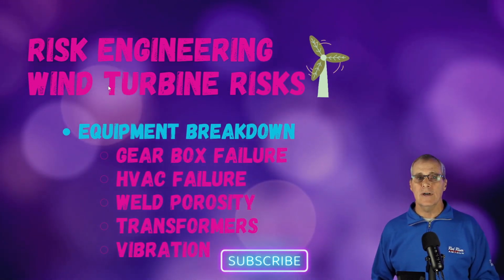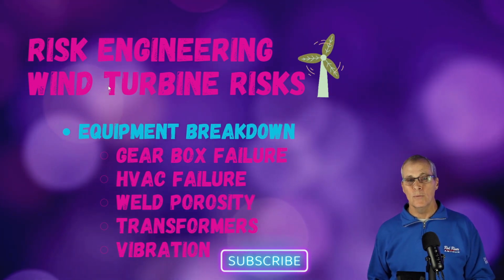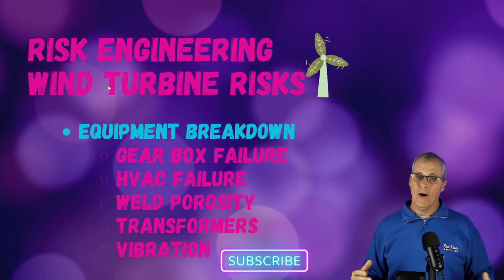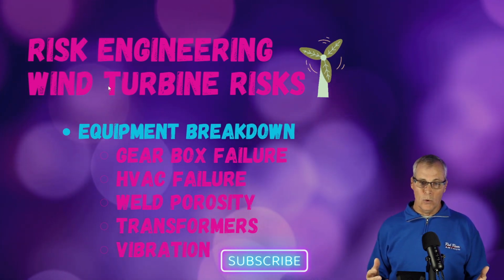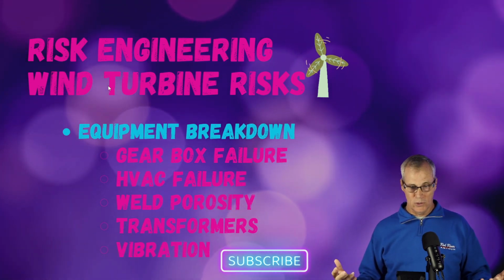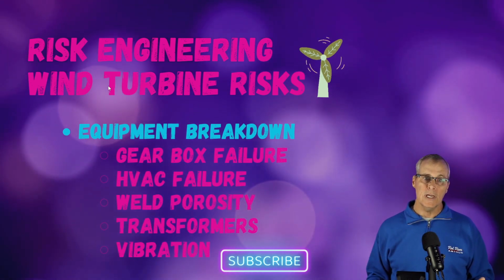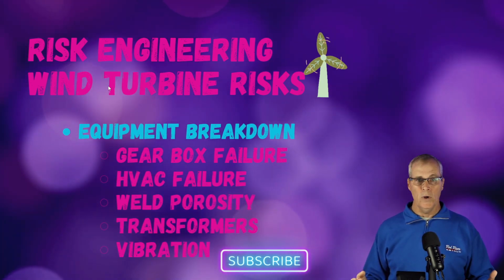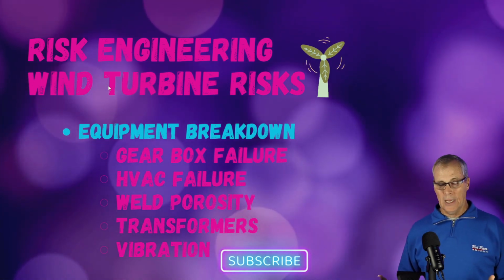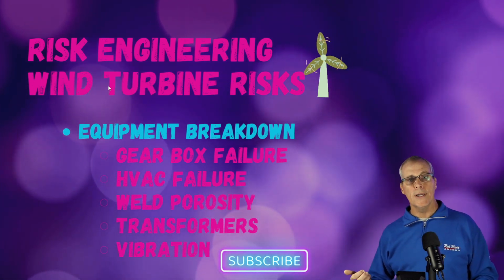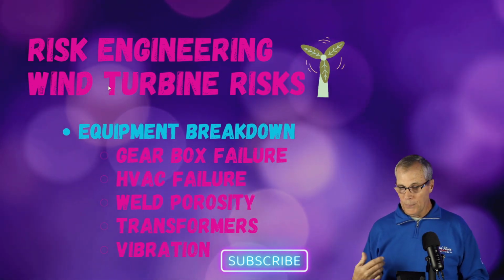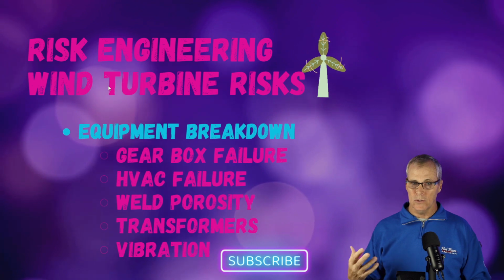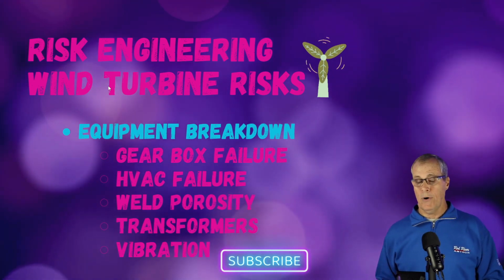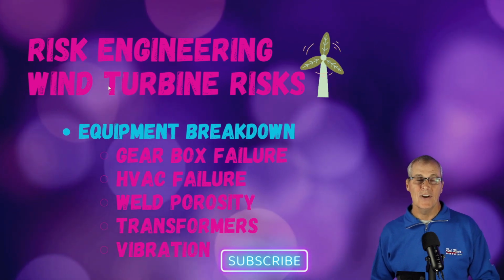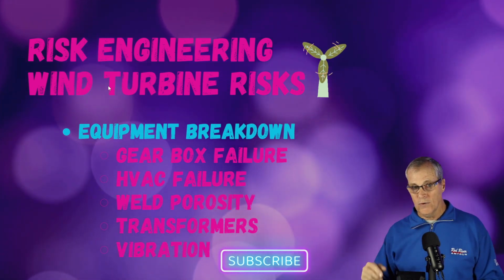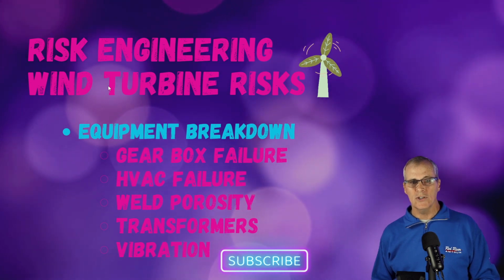We'll talk about transformers. We made a complete video on transformers and how to manage that risk. All power generation is made at a voltage other than the grid transmission voltage, so there need to be step-up transformers on site. All the transformers at a wind turbine or wind farm are subject to the same failure mechanisms: the oil breaking down, overheating, overloading, the paper breaking down. So dissolved gas analysis is your best friend, or really, partial discharge analysis is even better. DGA is there, but go watch the video on transformers to understand why partial discharge is even better.